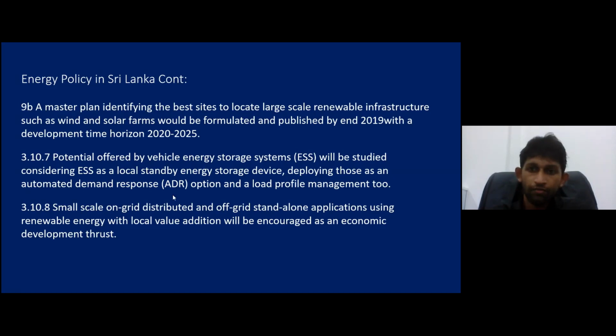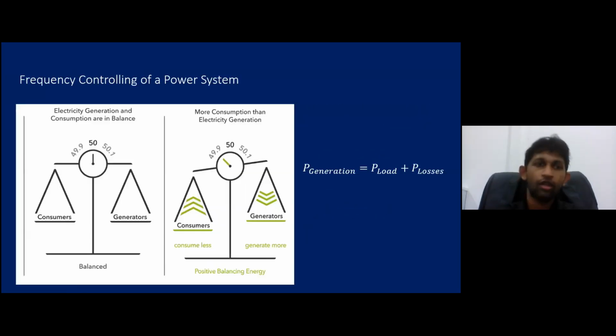Now, going to the topic directly of my presentation, we know that there is the power balance. The power generation should be equal to the power demand. When the demand increases and the generation stays the same, the frequency reduces. However, if the generation increases and the load stays the same, the frequency increases. So the best match is when the load and generation are the same. But what happens if a sudden generation loss occurs?